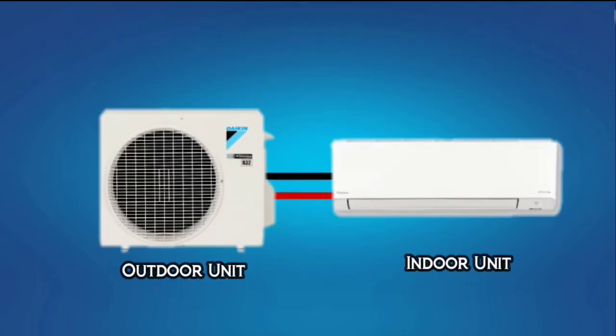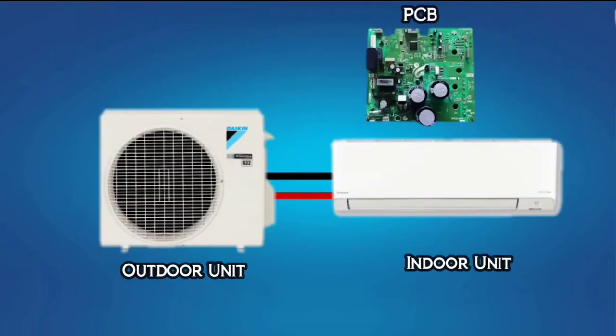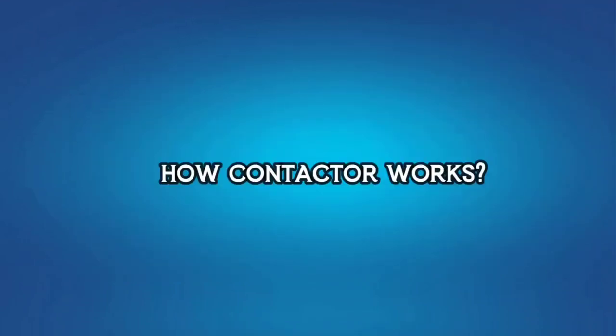In an AC, the signal is sent to the outdoor unit through the PCB in the indoor unit. High voltage power cannot be directly supplied to the compressor from the PCB. To avoid such safety issues, we use a contactor. Now, let's see how a contactor works.